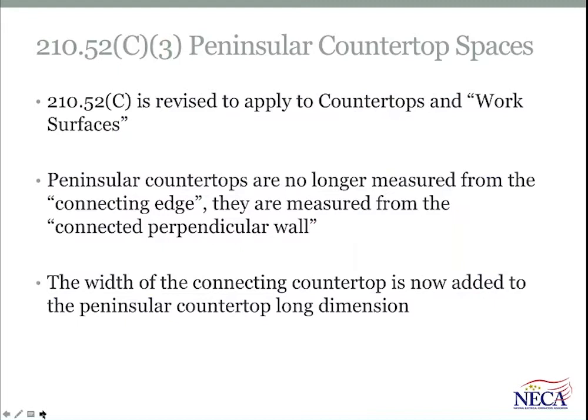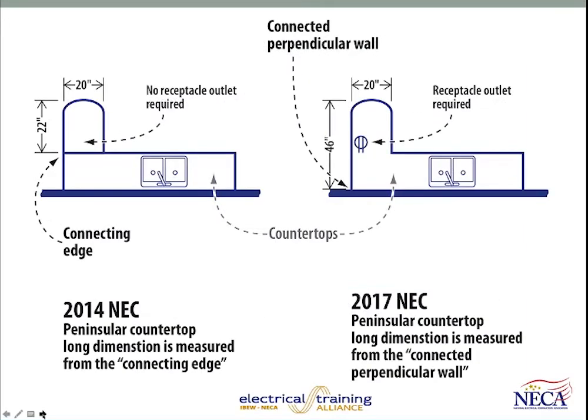Staying within 210.52(C), list item 3 has been revised to address not only countertops, but it also addresses work surfaces. And what was really changed here is the method of measurement when you're dealing with a peninsula countertop. No longer do we measure the distance from the connecting edge of the peninsula to the existing cabinets. They are supposed to be measured now from the connecting perpendicular wall. So the width of the countertop is now added to the peninsula countertop long dimension. We've got a graphic that goes along with that to show the comparison between the 2014 NEC and the 2017 NEC. Okay, so the measurement is not taken from the connecting edge anymore, it's taken from the connected perpendicular wall.